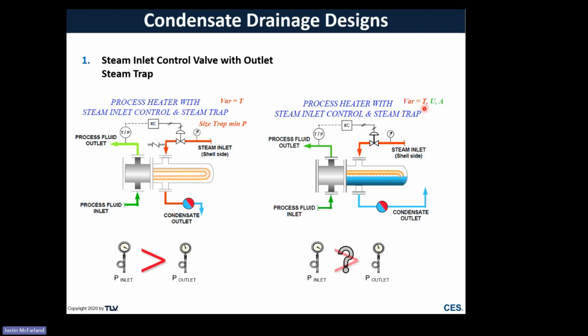And then while we're trying to modulate the steam temperature, some of the consequences of this scenario is that we end up with slow degradation in our U value because of corrosion, potential fouling on the process side because we've got hot temperatures here and cold temperatures here. We've got a loss of our A value. So oftentimes this results in lots of temperature swings to the process. The control valve might be very erratic as well as it tries to accommodate for the losses in BTUs that it's seeing on the process side. So there's a solution to this that we're going to be talking about later, but this is a scenario that we don't want to see.